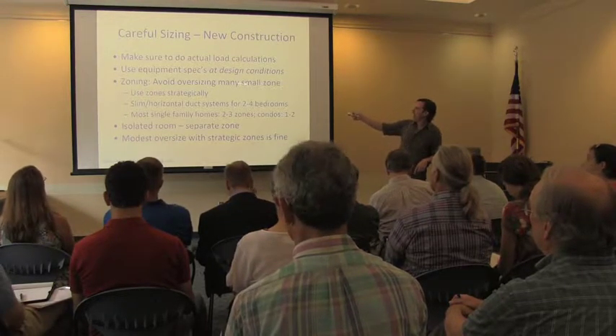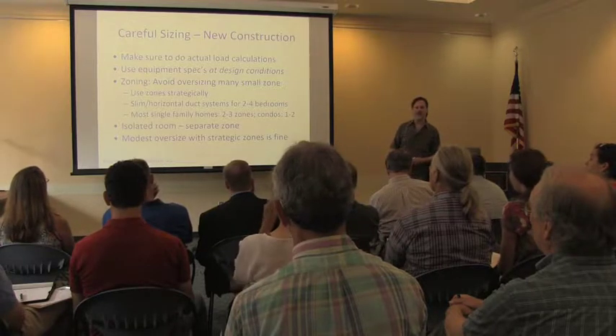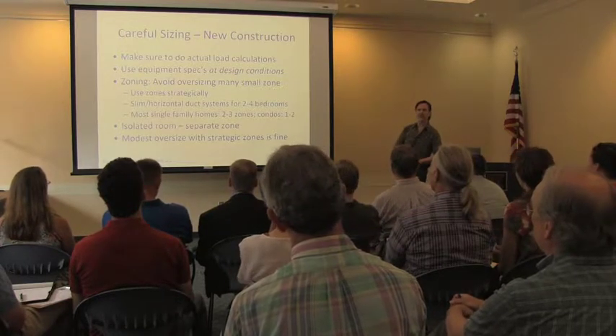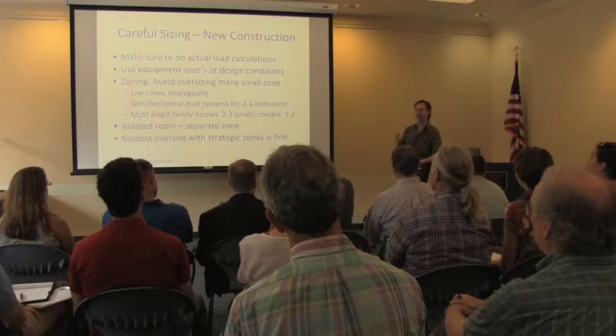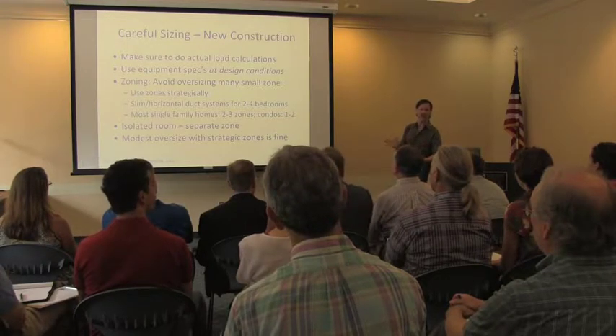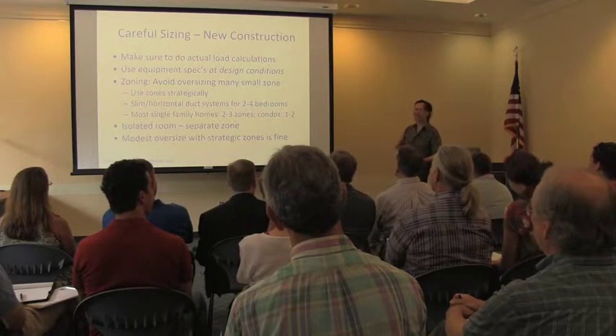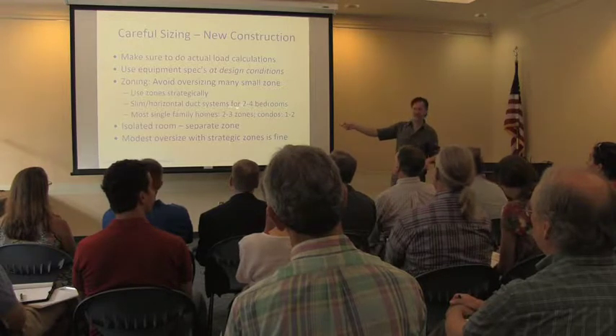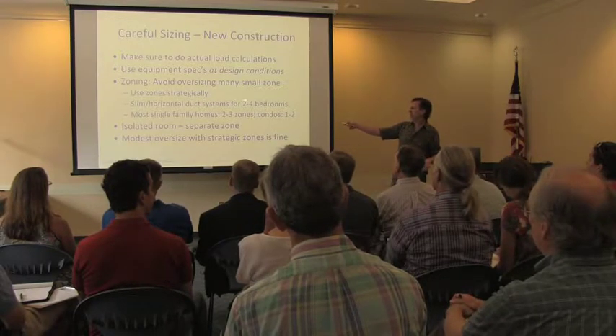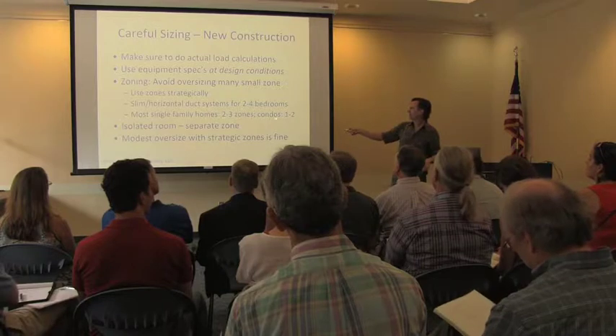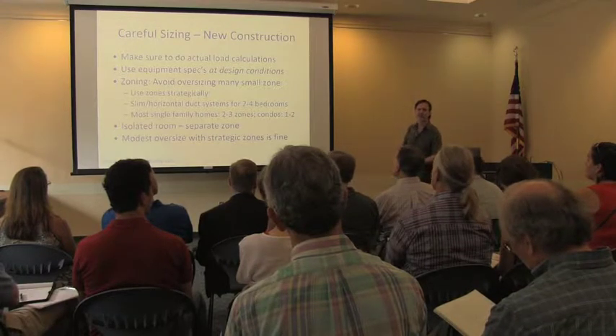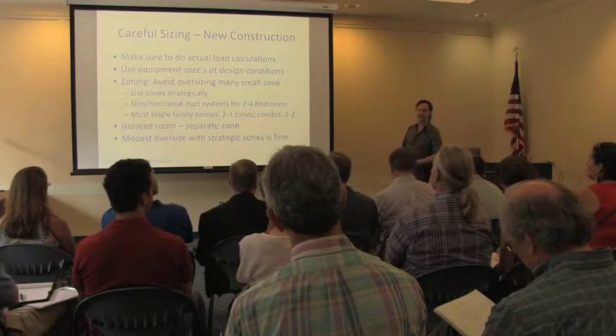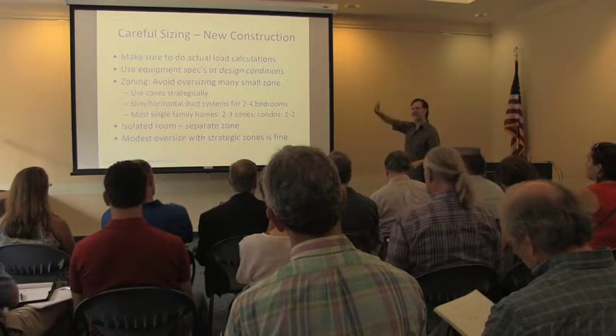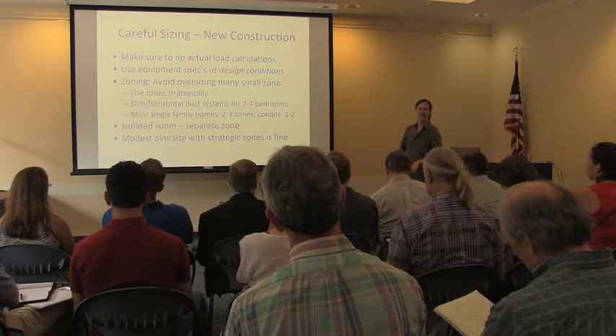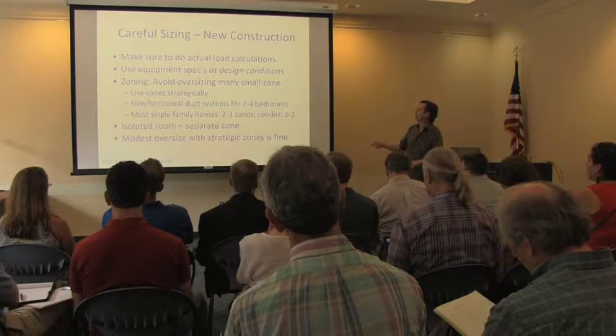I've been trying to emphasize to people, don't fall for the line of, hey, these heat pumps are great because you can put a zone in every single room and have individual room control. That's true, but it's an expensive way to go. I think it's much more important to use those zones strategically. For most houses, 2 or 3 zones; if it's a smaller property, a condo or an apartment, 1 or 2 zones is generally enough, as long as you don't have a space that's very, very isolated thermally from the rest of the building.